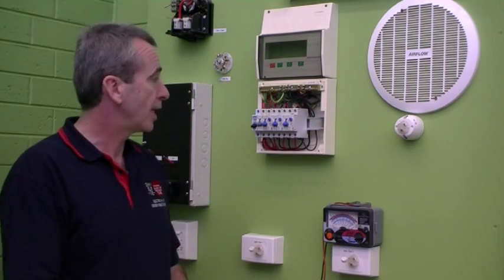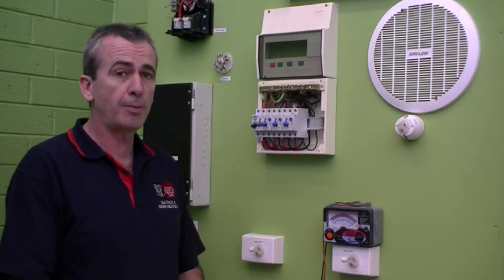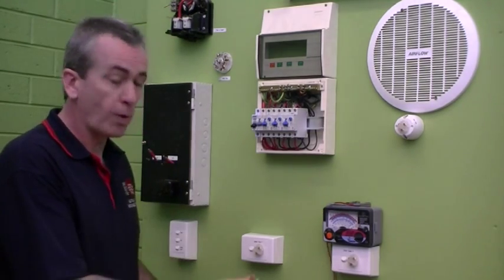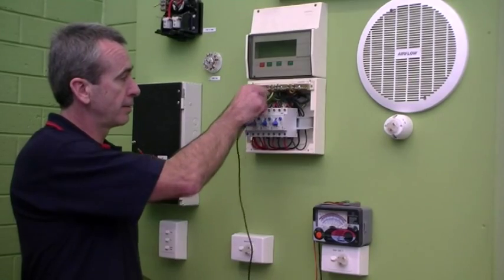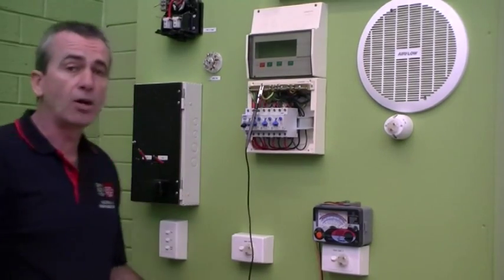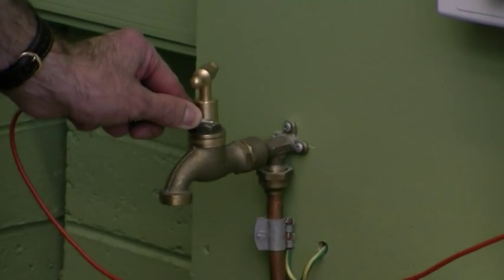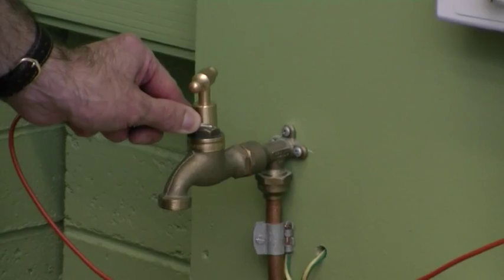I'll now test the resistance of the equipotential bonding conductor. That's the conductor that we hook up to the cold water pipe. On this installation, that conductor is run between the earth bar straight down to the water pipe. So with my meter, I'll put one lead onto the earth bar, and with the other lead, I'll go down to the water pipe. My reading there is about 0.05 of an ohm.